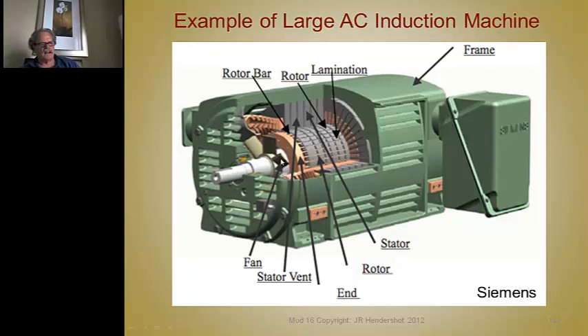One, this copper will suck air as it spins. These bars become centrifugal fan blades, and so it circulates air, and that air blows on the end of the stator winding. So not only does it cool the rotor, but it cools the stator as well. So you have built-in fans for free. But that's not the main reason this is done this way.